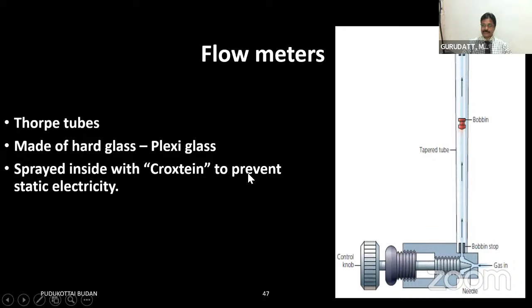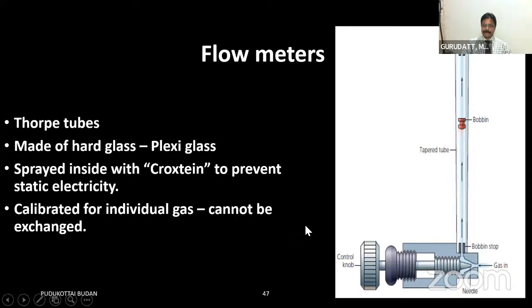So this is another exam question. Sometimes you'll be asked, you should be knowing about it. And the other thing is, these flow meters are calibrated for the individual gases, because each gas has its own viscosity and density. Based on that viscosity and density, the calibration is always done for the individual gas for the same flow meter. So if the nitrous oxide flow meter is broken, you cannot exchange it with an oxygen flow meter, because that is calibrated only for oxygen and not for nitrous oxide.